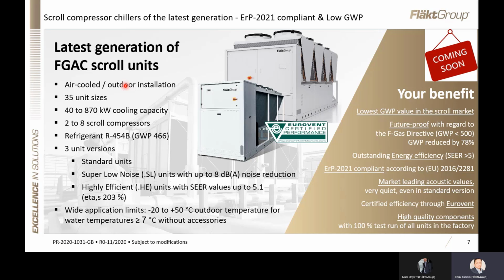Three unit versions are available: standard units, super low noise versions, which is the best available in the market, and a highly efficient version with a SEER value up to 5.1 and an ETA value of 203%. That will help the consultants to pass their energy modeling easily. And these chillers have a wide application limit from -20 to +50 degrees outdoor temperature, for water temperature greater than 7 degrees C, without any accessories.